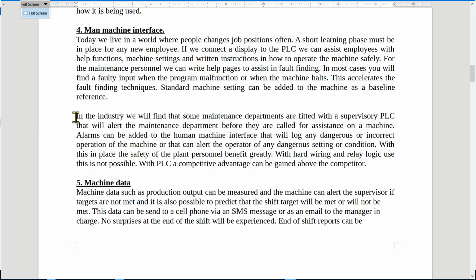Now, in the industry, we'll find that some maintenance departments are fitted with supervisory PLCs that will alert the maintenance department before assistance is even called for this machine. Now, even alarms can be added to the human-machine interface that will log any dangerous or incorrect operation of the machine, or they can alert the operator of any dangerous setting or condition. With this in place, the safety of the plant personnel benefits greatly. With hardwiring and relay logic, this is not possible. But with the PLC, a competitive advantage can be gained above the competitor.